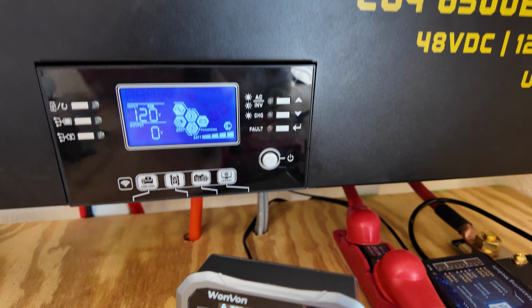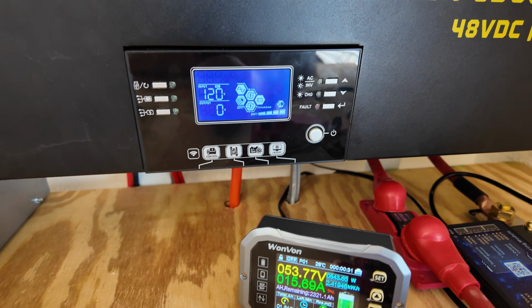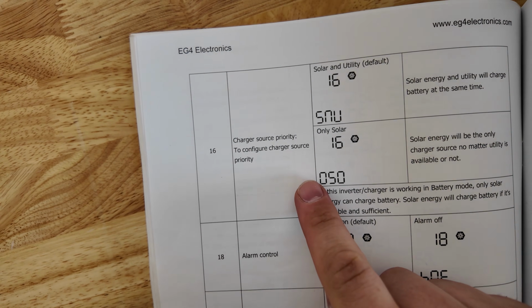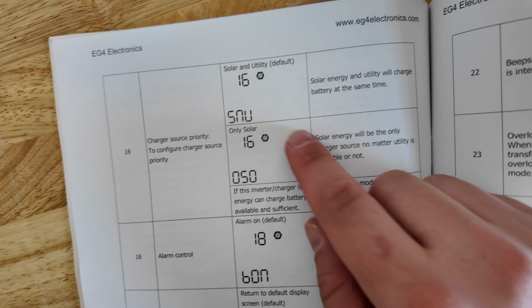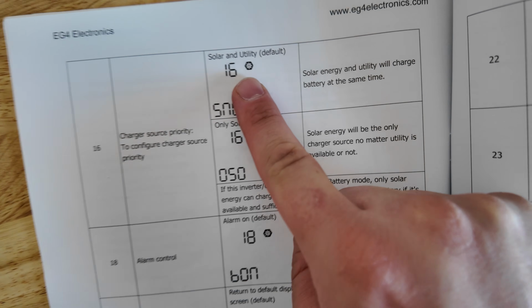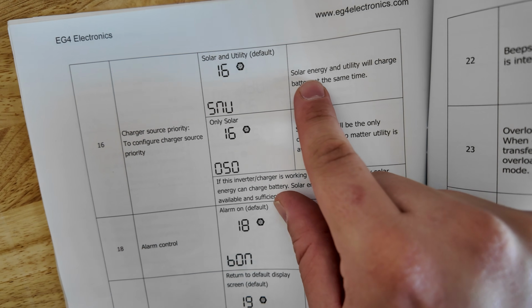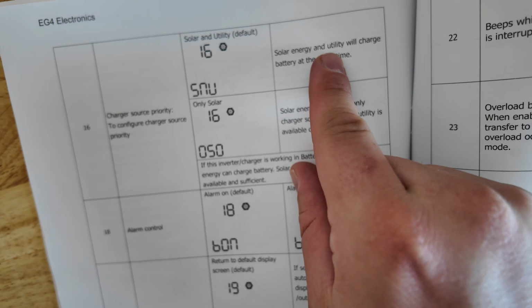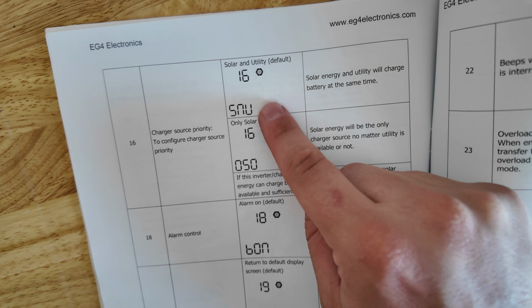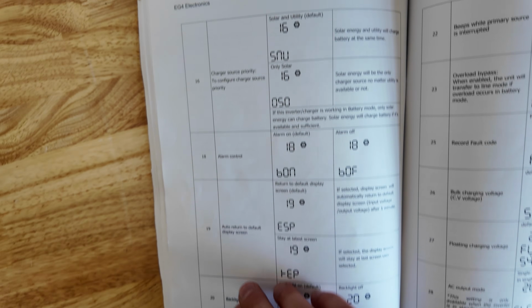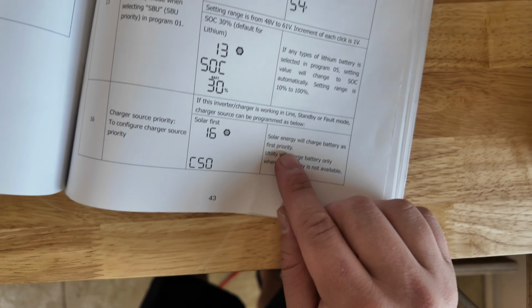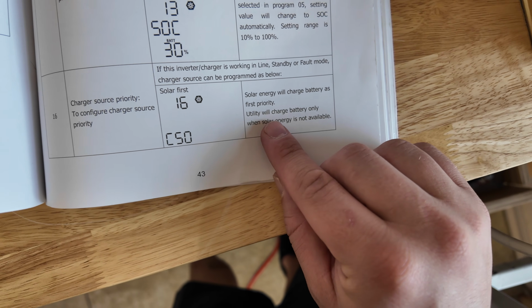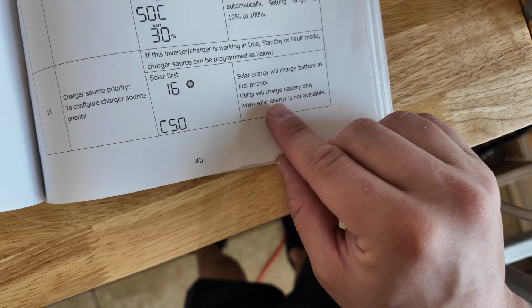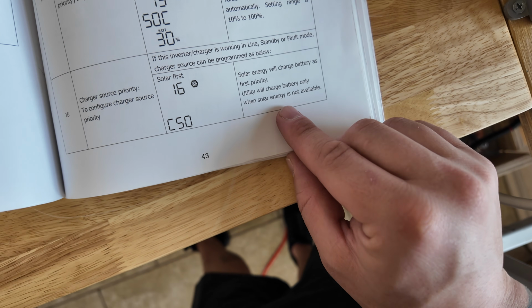Alright, so it took a little searching through the instructions, but I managed to figure it out. We have setting number 16 in the book, which says to configure charger source priority. This one is supposed to be set to default, but for some reason it was not. It says solar energy and utility will charge the battery at the same time, and that's the setting I was missing. It was set to solar energy will charge the battery as first priority, utility will charge the battery only when solar energy is not available.